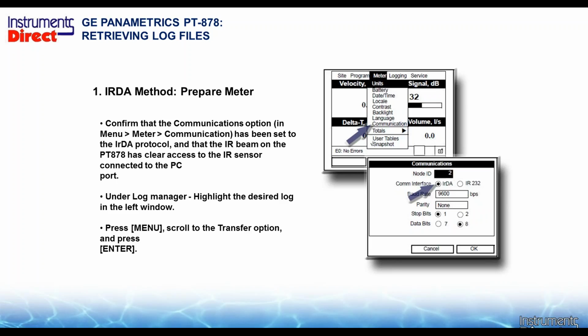So for the old infrared sensor on the top, what we need to do is go into the communication option, and we need to make sure it's set up for the IRDA protocol. And that basically means the beam on the top of the PT878 is a little window, little red window, and has clear access to the IR sensor that's connected to the PC. We'll show you what that looks like in a minute. And under Log Manager, highlight the desired log in the upper left-hand window. Press Menu, scroll to the Transfer option, and just press Enter.